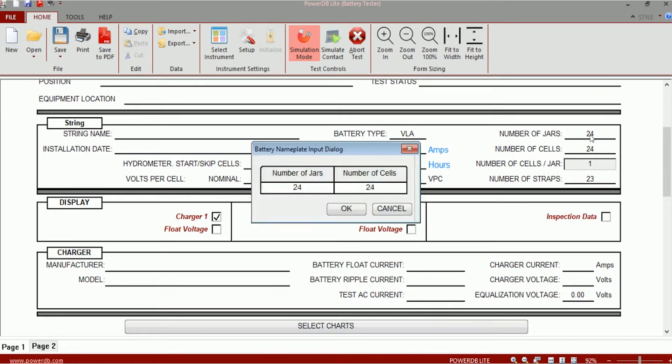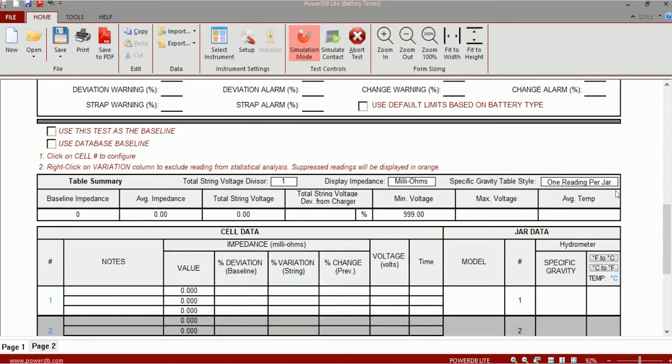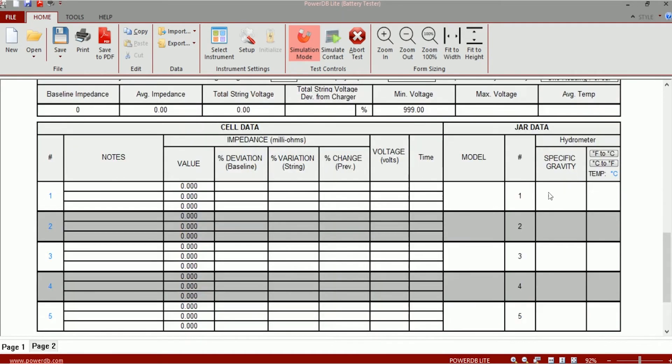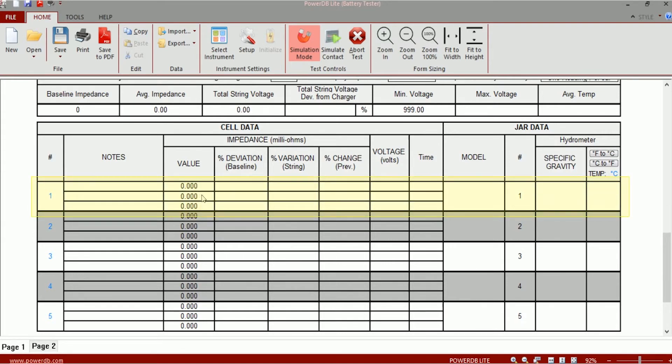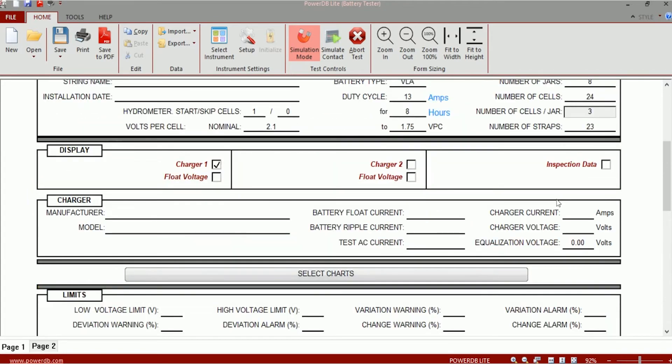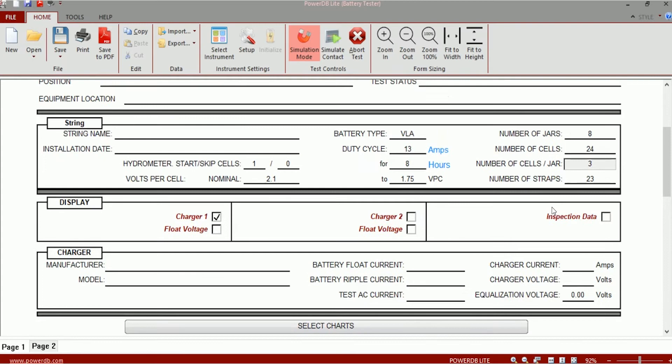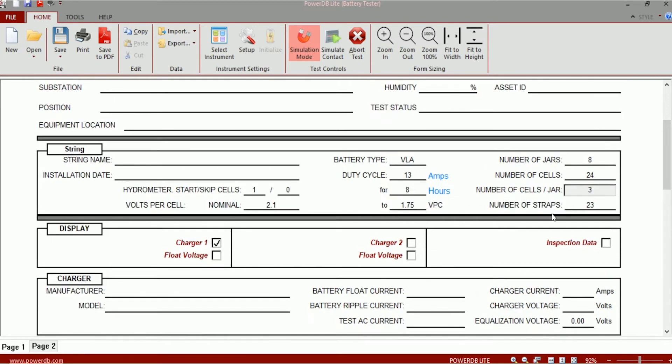If I was to edit this and say that the string consists of 8 jars, then the number of cells per jar now changes to 3. And on the test table you can see that it says jar number one and there are provisions for three impedance values, one for each cell. There is one cell for specific gravity for each jar. So that's how the test table changes when you change the number of cells per jar or when you edit the number of cells per jar.